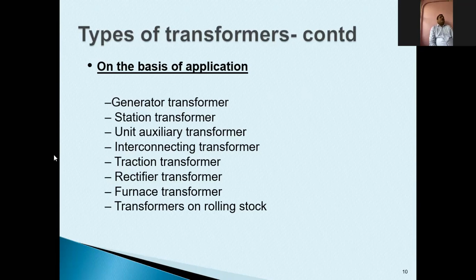So now, can you calculate the cross-section area of the conductor required for carrying 20,000 or 15,000 amperes of current? Generally, in a generator transformer, due to such a high current rating, there will be higher I square R losses. So to reduce the R part of the conductor, we keep the cross-section area more, because again, resistance R is equal to rho L by A. Rho is the resistivity of the conductor material. L is the length of the conductor, which will again depend upon the design of the transformer or the voltage of the transformer. How many turns do I have to put? What is the diameter of the core which I have to keep there?